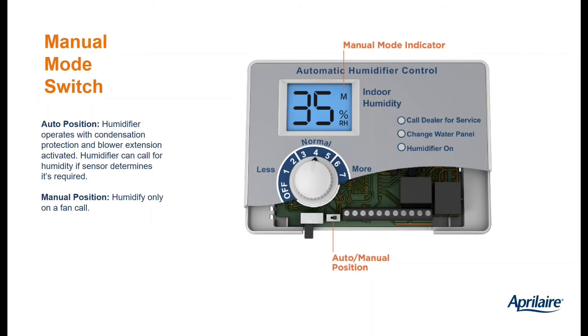We talked earlier about the main advantage of the automatic humidistat, which is the outside temperature sensor. The outside temperature sensor is what makes it an automatic humidistat, because it can automatically adjust its RH set point. If you choose not to use the outdoor temperature sensor, you can still use the Model 60, but you would run it in manual mode. So if you're not using the outside temperature sensor, you can run the Model 60 in manual mode. This has nothing to do with blower activation. On the inside, there's a little switch labeled auto and man. Just push that little switch over to the manual position. What that does is it tells the humidistat that it's always 20 degrees. So you don't need the outside temperature sensor.